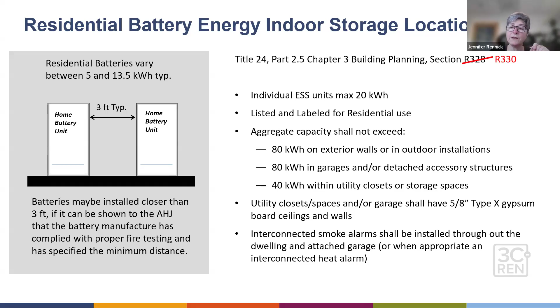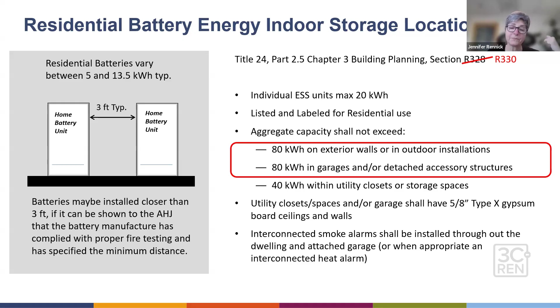So 2025 code now, you're going to look for that in residential section 330 - they changed the section on us. Where you used to only have 80 kilowatt hours altogether - 4 individual batteries if each is a 20 kilowatt hour max - that's a lot of batteries, but now the code is more nuanced, with a new table to go with it, and it really depends on where it's located.